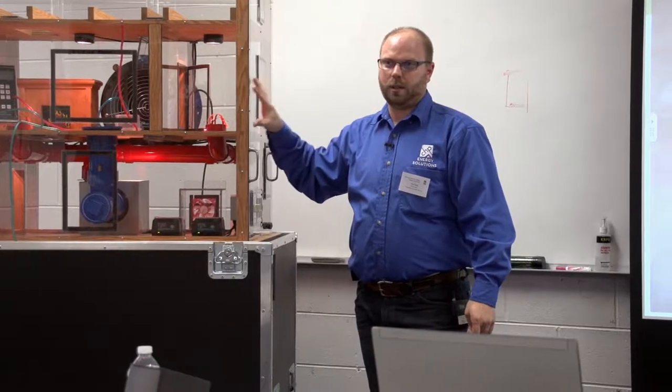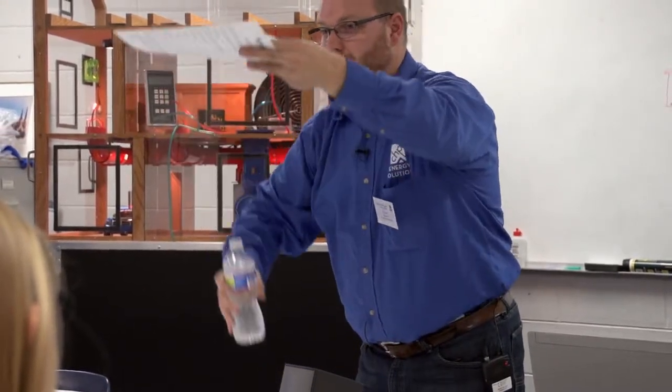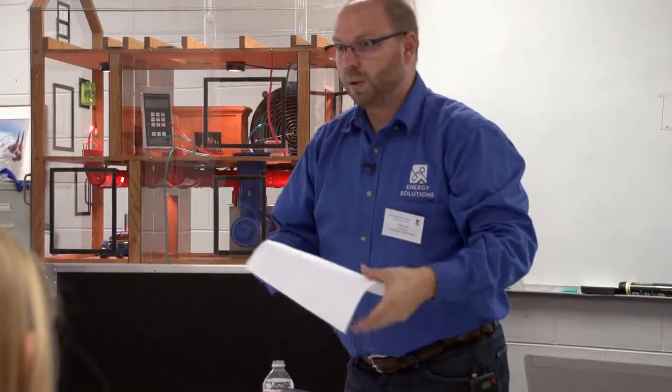That's the biggest push of moisture into your home, because vapor diffusion is very slow. And I could demonstrate that very simply here. Hold up this piece of paper above your head, okay? And I'll pour this out on this piece of paper. That's diffusion. Now, cut a hole in this. Okay? That's air movement. Diffusion takes longer because you have to saturate every molecule in that membrane before it'll move to the other side. Complete saturation. Movement of air, you just need a hole, a clear passageway. There's no restriction. Pressure difference. A little bit of wind, a little bit of pressure difference, turn on the bathroom exhaust fan, boom. You brought all that moisture right into your house.